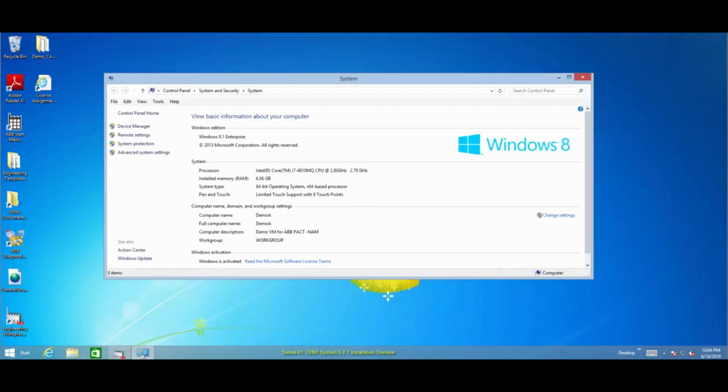The Compact HMI new installation has three phases: prepare, setup, and configure. The main purpose of the prepare phase is to configure a node to be a Compact HMI node. During the prepare phase, activities such as selecting and installing the Windows operating system, configuring network adapters, configuring users and groups, setting up the other third-party software, and preparing the node using the node preparation tools are implemented.